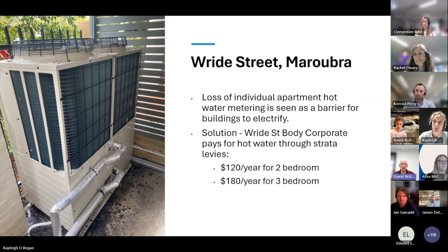A couple of other challenges we had. We were retrofitting a 4-boiler gas system, which is pretty much where we've got our storage. So I'd say we're probably doubling the space of storage, probably not quite 3 times what we had with the gas system. As you can see there, the Q-Ton heat pump unit sits outside. It's actually under a balcony, but sits outside, so we're making use of ambient air. There's been no real issues with that. It runs very quiet, pretty much like a modern house air conditioner. So it's very, very quiet.